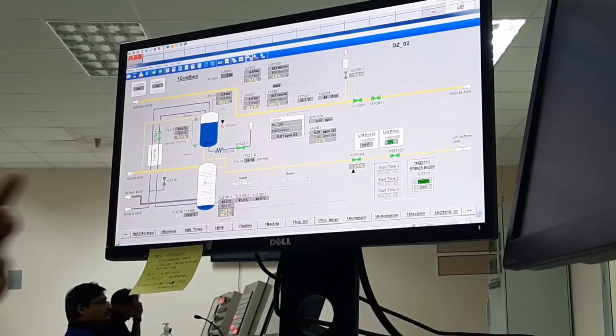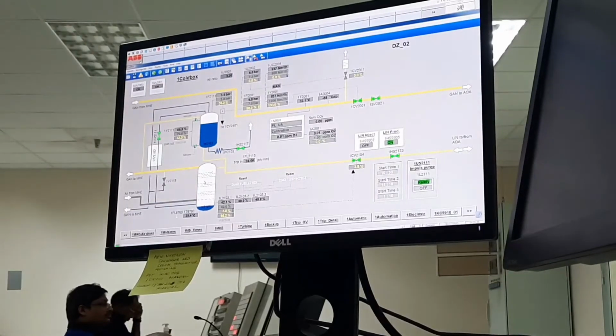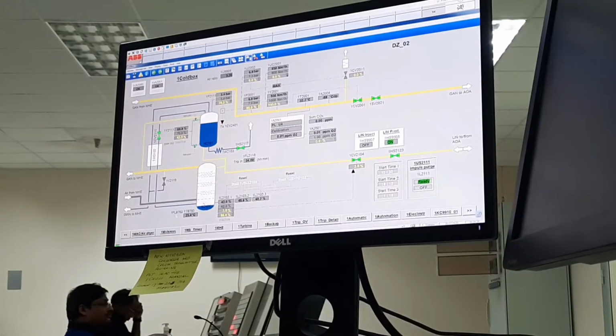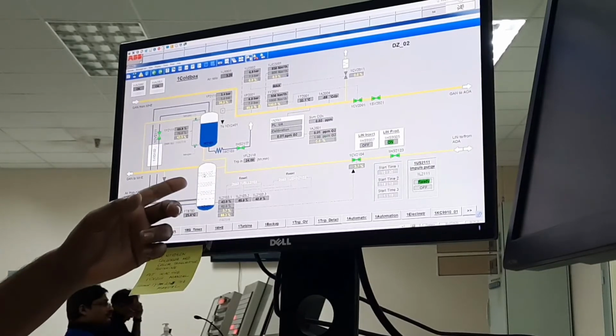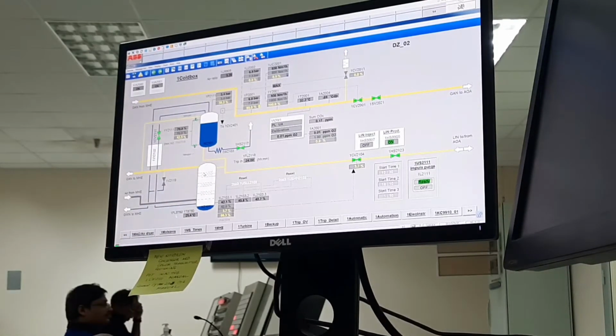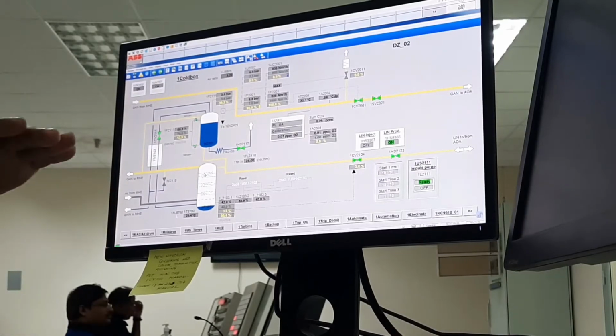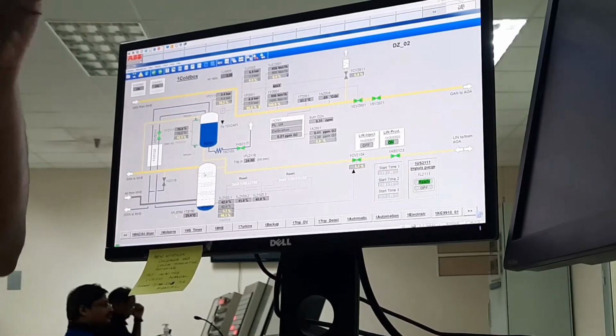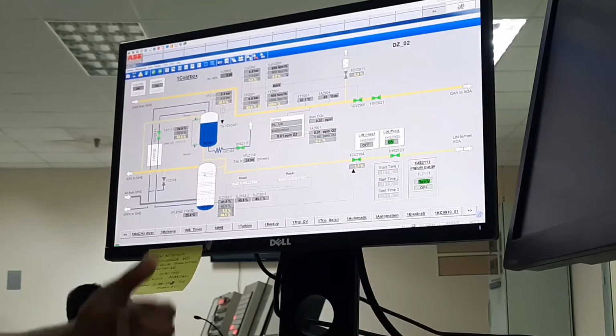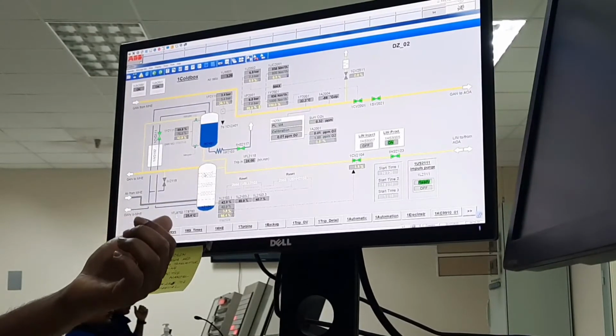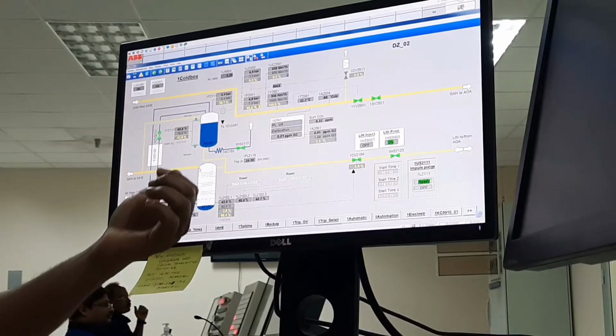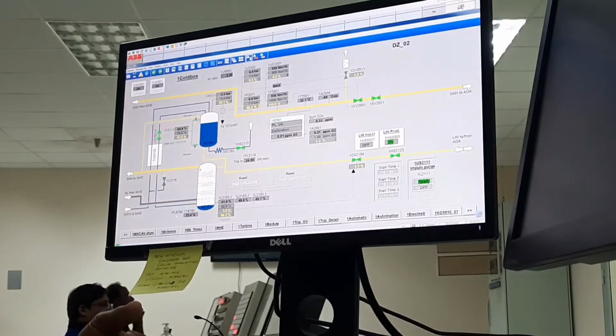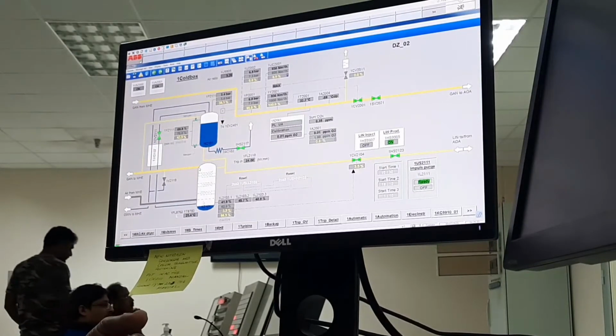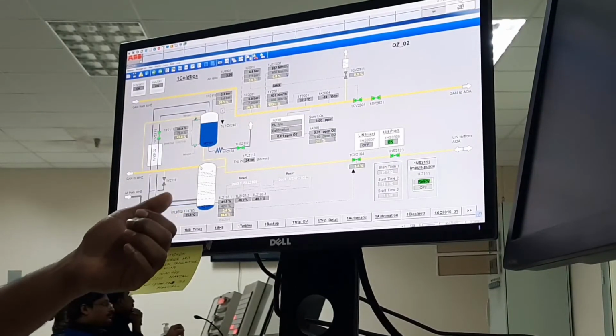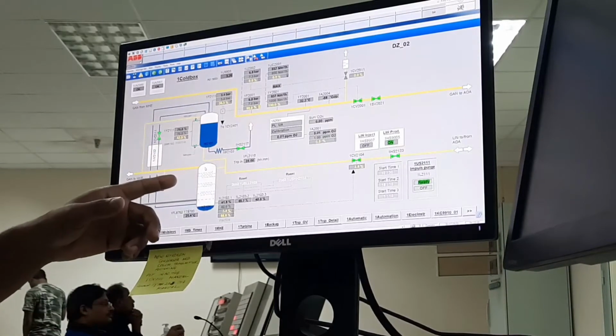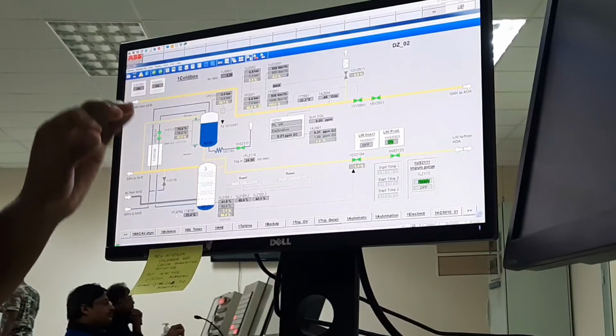Mr. Khalid, so the rectifier column also has 50 trays. So when the air goes through the trays, the pressure should also reduce. Yes, because they obstruct; when it goes through the process there is some obstruction. For that reason the pressure and temperature should reduce. Normally this temperature is minus 168. When it passes by the top side, the temperature will come down to around minus 170 degrees. So when this 3000 air passes through the rectifier column, the temperature reduces and the pressure also reduces a little.